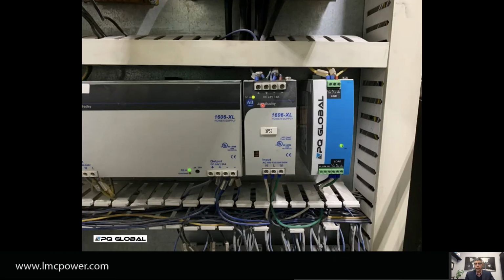We actually have some readings for this. If you see these yellow cables up on top, those yellow cables were previously connected to the input of this power supply, okay? So without the surge protector, we just had current coming in directly into the power supply. What we've done is we've disconnected it from here and put in our surge protection. This one's called a DSF, a DIN surge filter. It's a DIN rail type surge filter, so it has 2 functions.